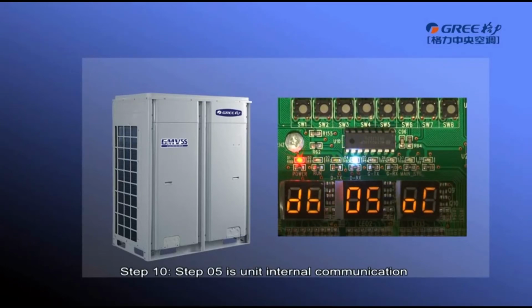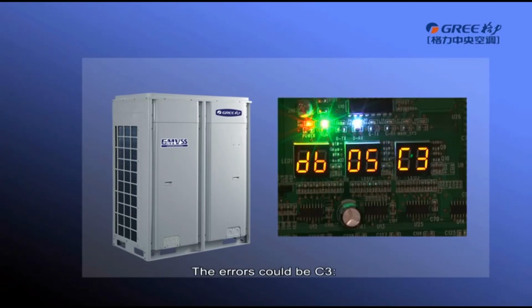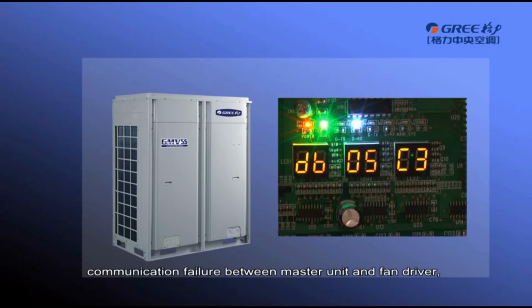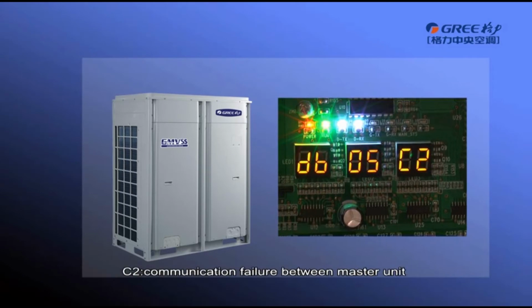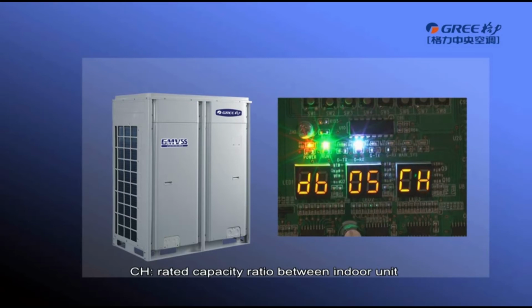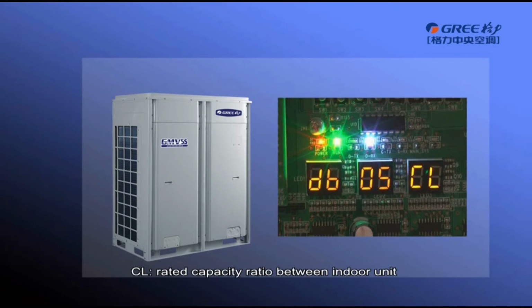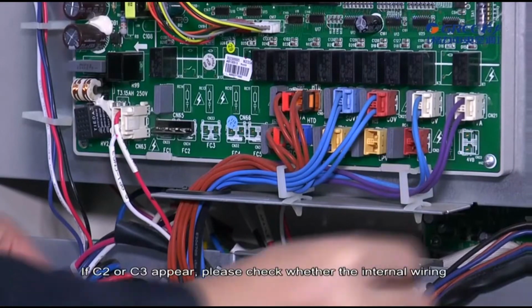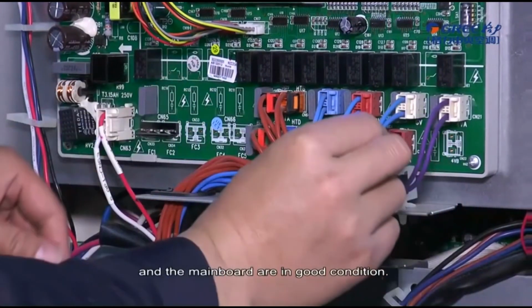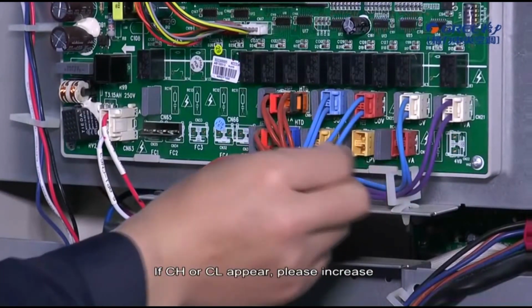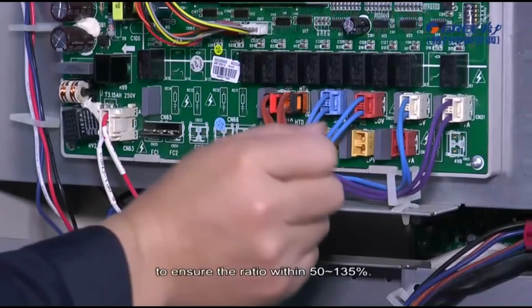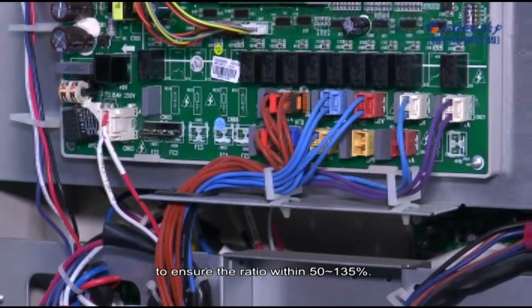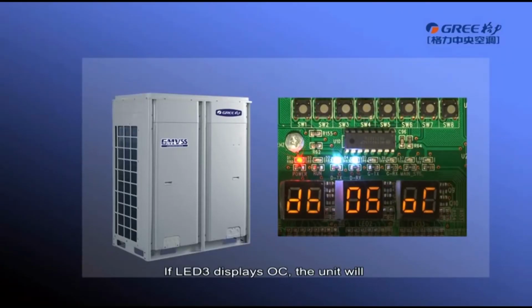Step 5 is unit internal communication and capacity matching detection. If the detection is abnormal, the unit will retain the current status. The errors could be C3, communication failure between master unit and fan driver; C2, communication failure between master unit and compressor driver; CH, rated capacity ratio between indoor unit and outdoor unit is too high; CL, rated capacity ratio between indoor unit and outdoor unit is too low. If C2 or C3 appear, please check whether the internal wiring and the main board are in good condition. If CH or CL appear, please increase or decrease indoor unit quantity to ensure the ratio is within 50 to 135%. If LED 3 displays OC, the unit will enter step 6 automatically.